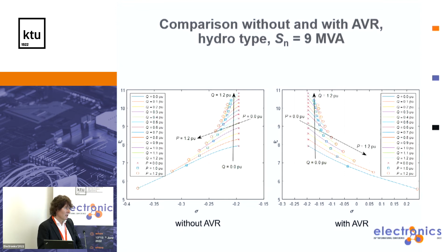We tested this many times, with different synchronous generators, and we saw that always with a hydro type synchronous generator, we have this phenomenon. So always if we increase P, the damping will decrease completely. This is the consequence of introduction of the automatic voltage regulator. Very dangerous.